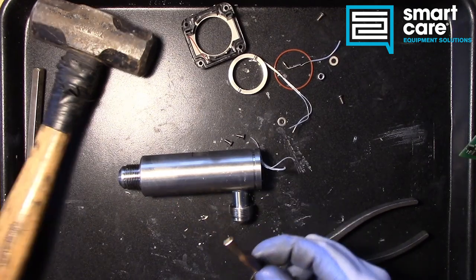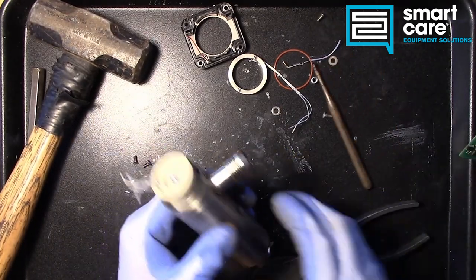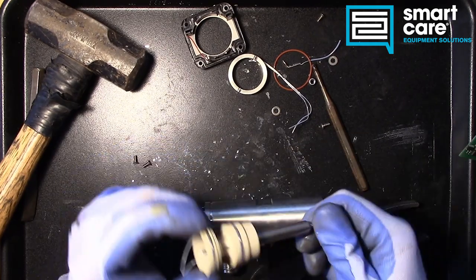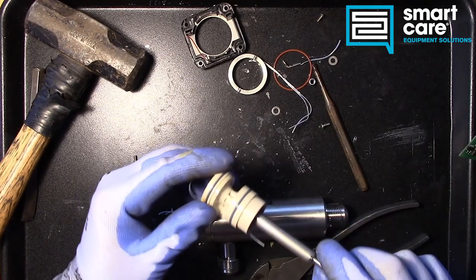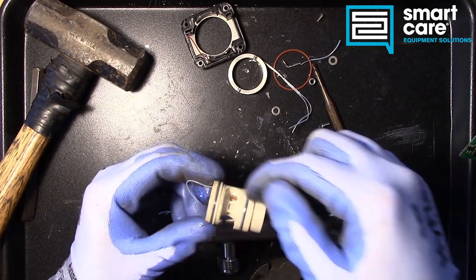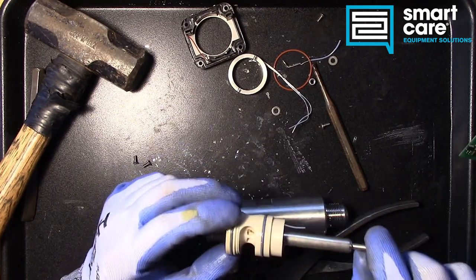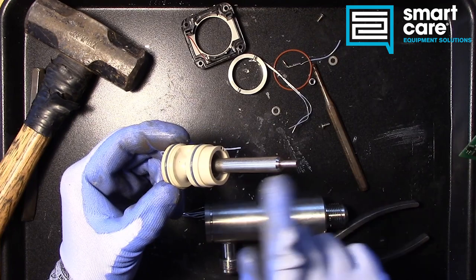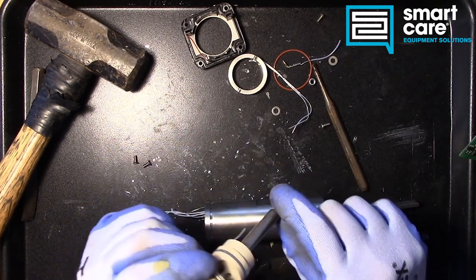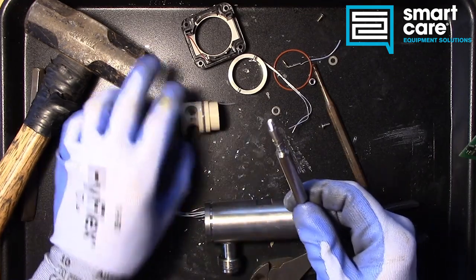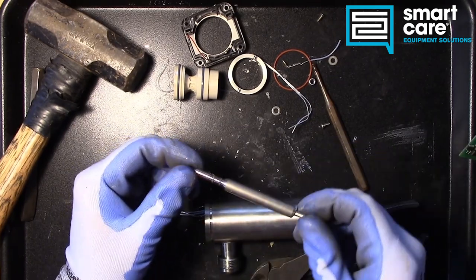I took this drift punch and ran it down through the center here. This thing is almost like a rivet, it feels like. All right, so here's what we've got inside. An oil control, and this thing is oily. So there's a central cylinder here. You can see there's some debris stuck in this. So somebody ran this without filter paper at some point. The oil is moving through this in a way that it's creating flow down across this part of the device. So there were wires that came up out of here. We can try and cut this apart, but I don't know how much success we'll have. I am assuming this is a temperature sensor that's making sure that we have the correct oil temperature as this thing is operating.